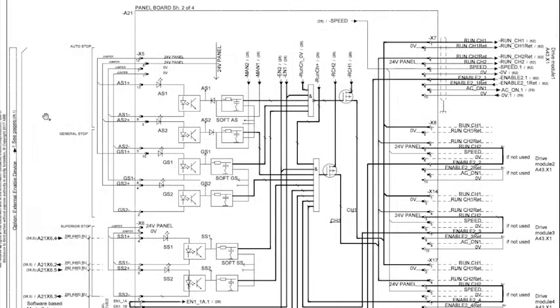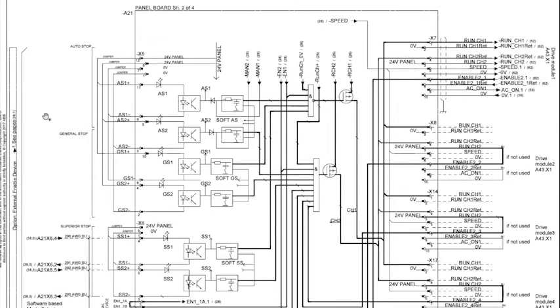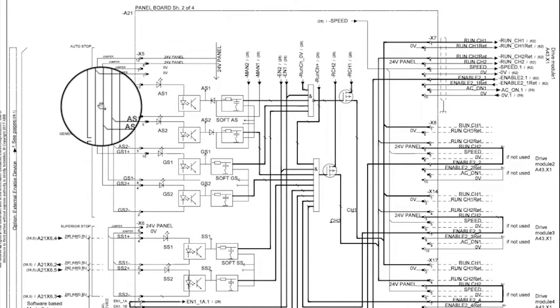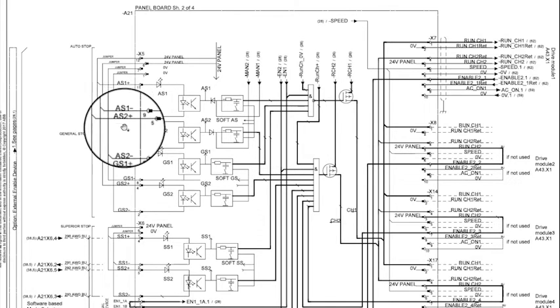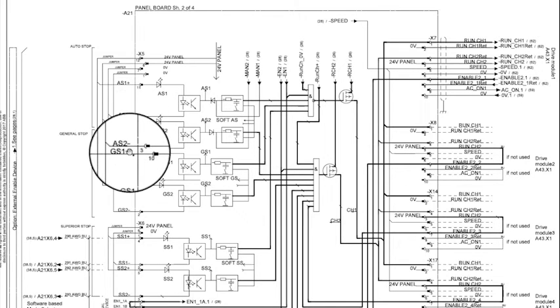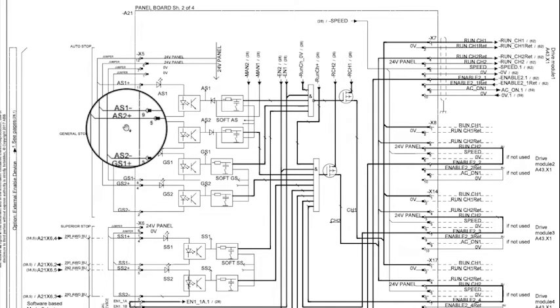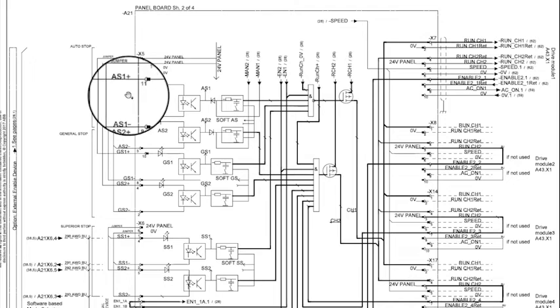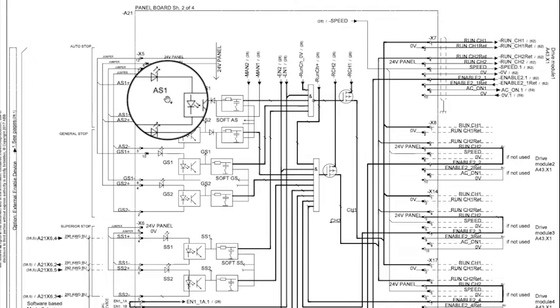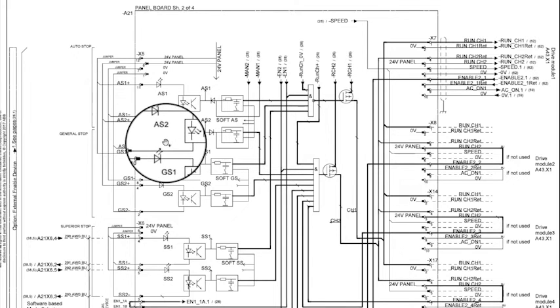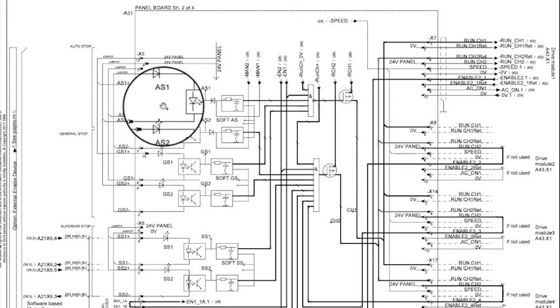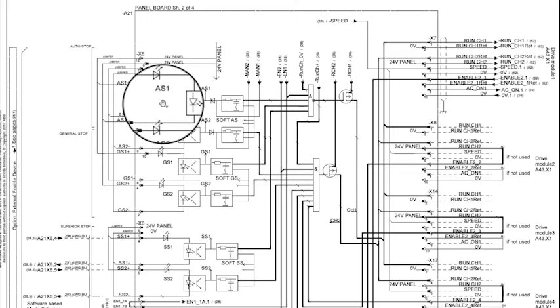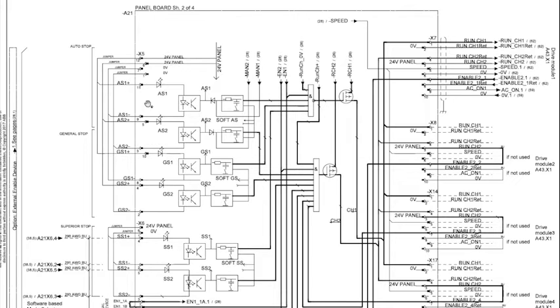Our auto stop safety chain is a dual channel chain which requires each channel to be broken at the exact same time. If AS1 channel is broken before AS2 channel, then the controller will provide a fault in reference to inconsistent timing of the signals.